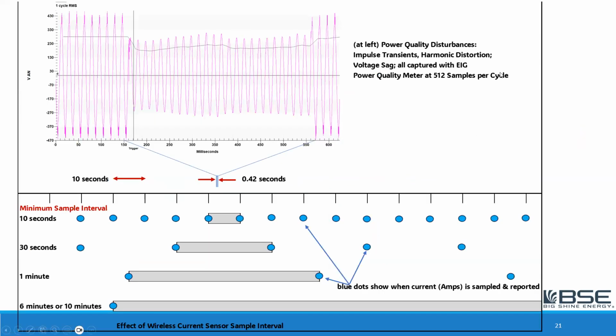Now, if you get a disturbance, I mentioned that I would show you waveforms to show you what bad power quality looks like. This is a single phase that I'm looking at. The meter was measuring all three phases, but I just took a snapshot of one phase. And if you look at the crest of the sine wave to the left, you can see that it's all irregular and spiky. It shouldn't look like that. That's ring transients and impulse transients, which are almost instantaneous little spikes in voltage, and then they come back down. But then there was a sag.